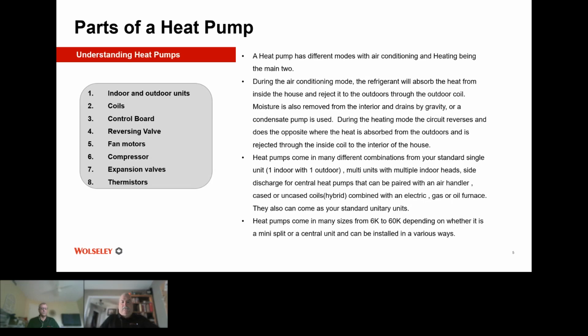Expansion valves. One of the most commonly used today is the electronic expansion valve, better known as EEV, and some still use a TXV, thermal expansion valve. This controls the flow of refrigerant throughout the system, and it opens and closes according to the demand. Then you have thermistors on both the indoor and outdoor units, which change in value. The main control board knows what to do with the value that it reads.